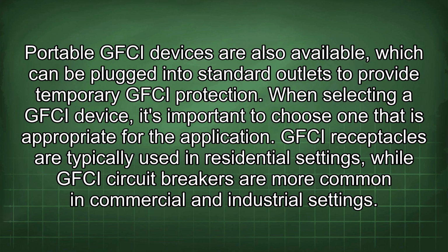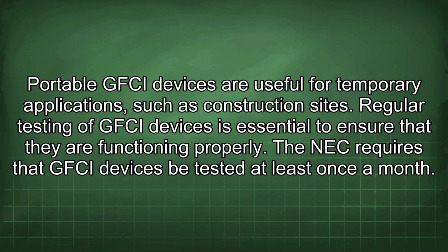When selecting a GFCI device, it's important to choose one that is appropriate for the application. GFCI receptacles are typically used in residential settings, while GFCI circuit breakers are more common in commercial and industrial settings. Portable GFCI devices are useful for temporary applications such as construction sites.